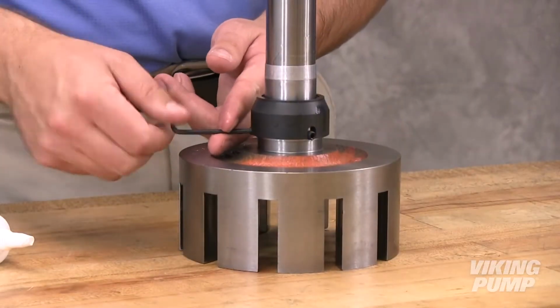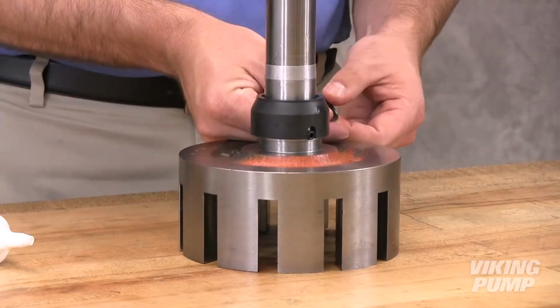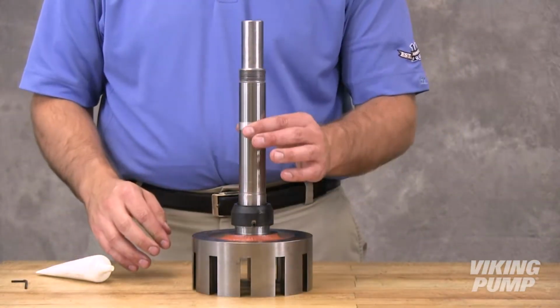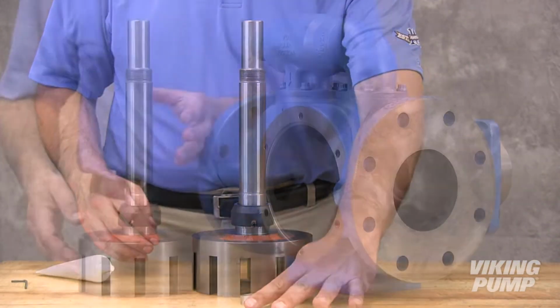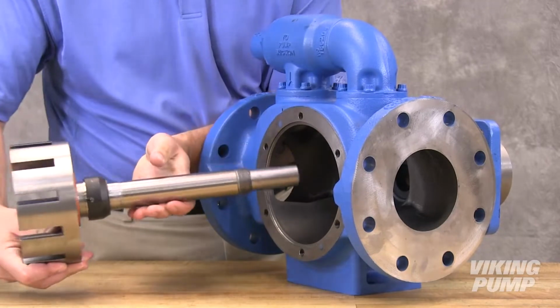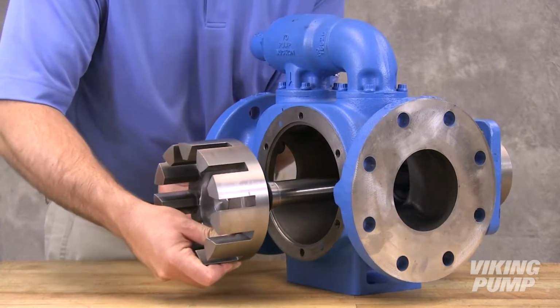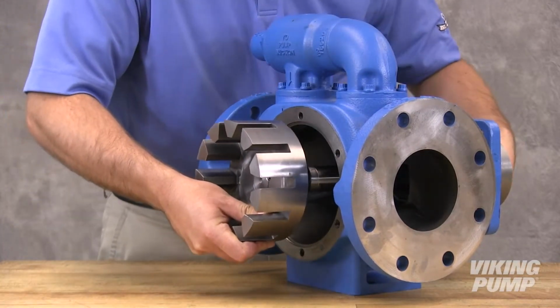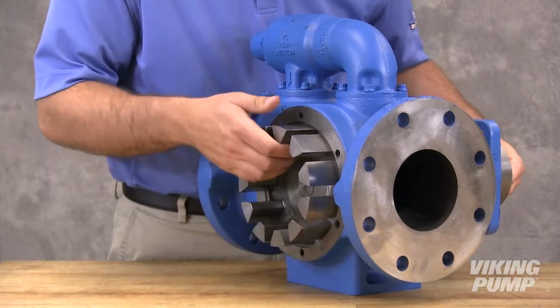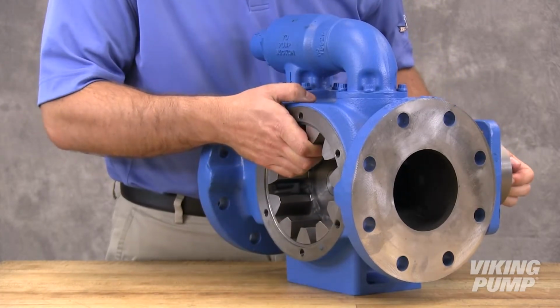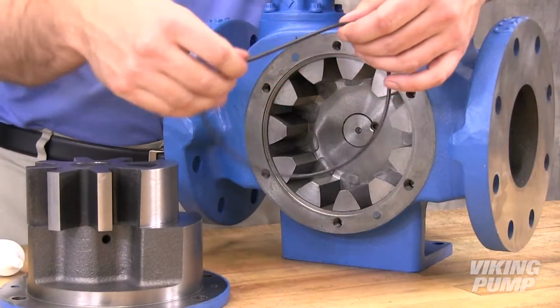Next, tighten the seal set screws evenly. Remove the installation sleeve. Next, install the rotor shaft into the casing. Slide the rotor shaft until the rotor teeth are just below the face of the casing. Take care not to damage the seal seat. Lubricate and install the head O-ring.